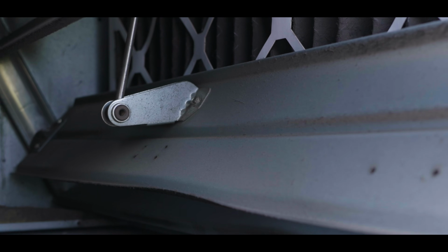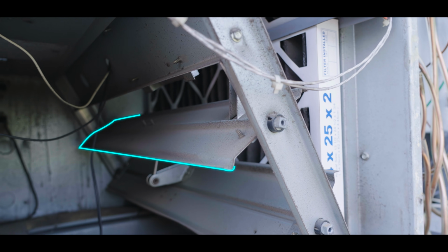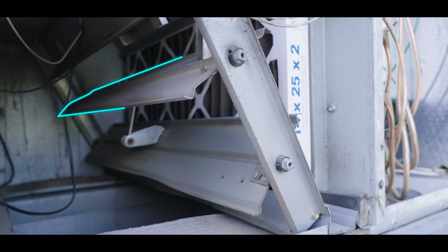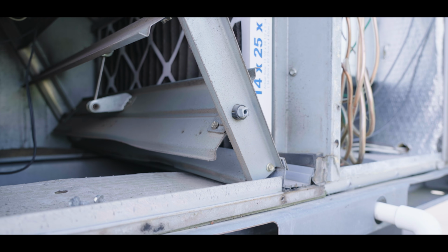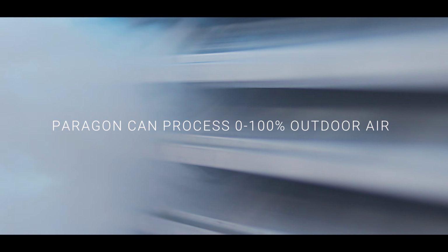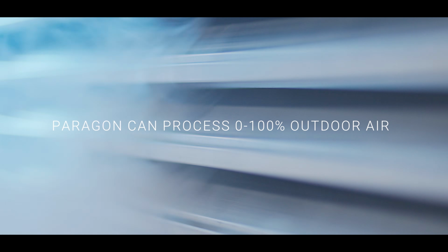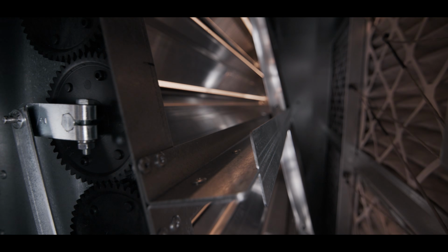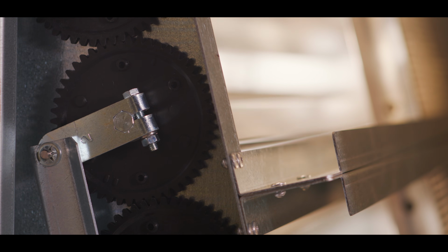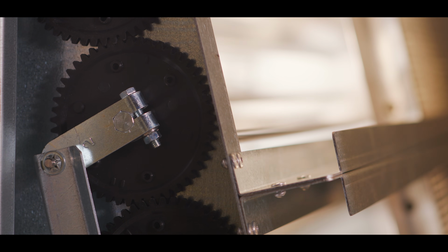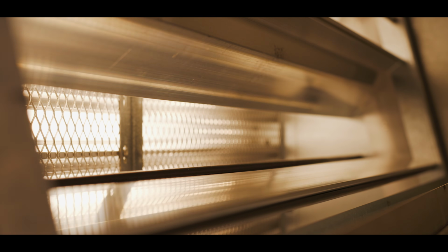We interviewed one producer of RTUs. We asked them why there was so much play in the damper blades. So when you say you're introducing X amount of outdoor air into a building, say it's 20% outdoor air, and those damper blades can actually move, how do you know you're actually delivering 20% outdoor air when the damper can fluctuate? So we selected a damper that didn't have that play in it. The gears are interlocking and they lock to a specific place, ensuring an exact amount of air quantity coming into the building.